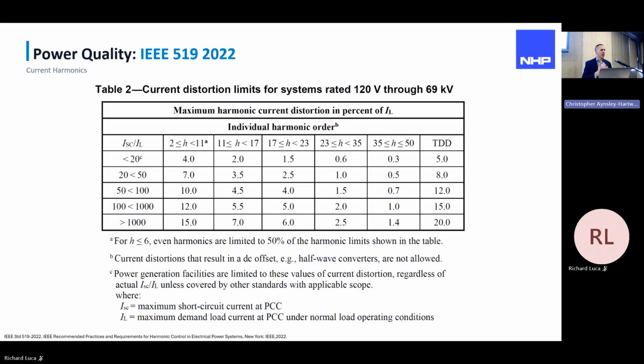With the current harmonics, the IEEE 519 standard, we're looking at this table here, which gives us the short circuit ratio and the load current. So for the facility, we'll work that out, move it across, and we're given a total demand distortion limit for the facility at the PCC. And for any power generation facilities where you've got renewables that are generally over about 10% of the load demand, you'd need to comply to the lower limit.